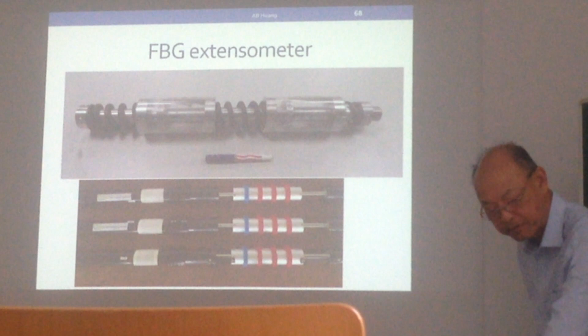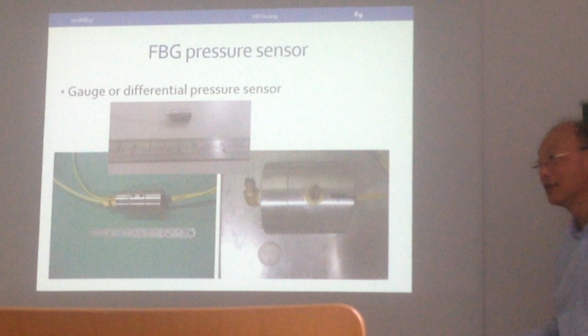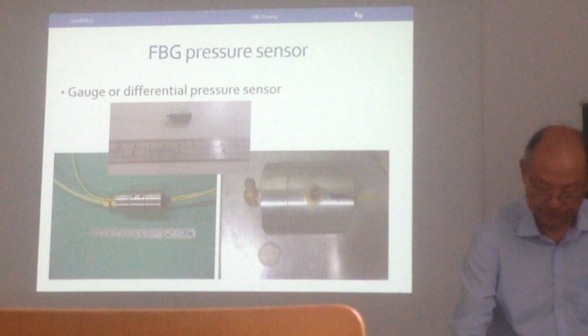Pressure sensors. This is probably what we made the most, over 1,000 of them already. From very large ones, this is an extremely sensitive differential pressure transducer. We can measure the water fluctuation within a fraction of a millimeter. This is the coin. You can see how big it is. This is regular size. You typically measure pressure in the range of a few hundred kPa. This is a miniature pressure transducer. It's about 12 millimeters in length, 7 or 8 millimeters in diameter. We make this specifically for centrifuge physical modeling tests, so we can bury this small sensor along with this tiny optical fiber cable in physical models.